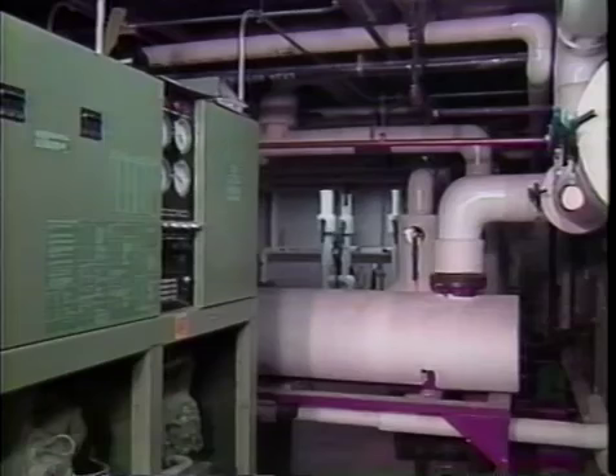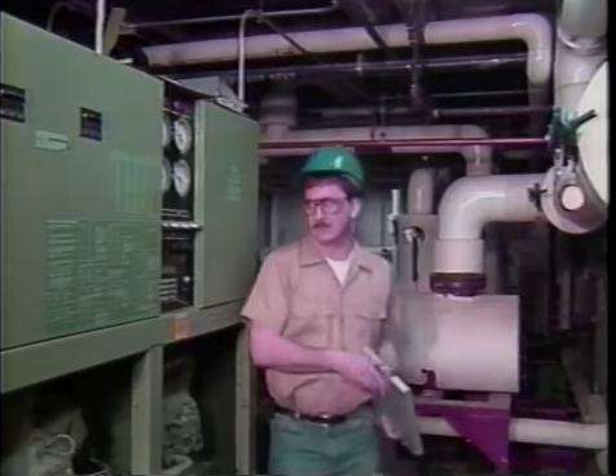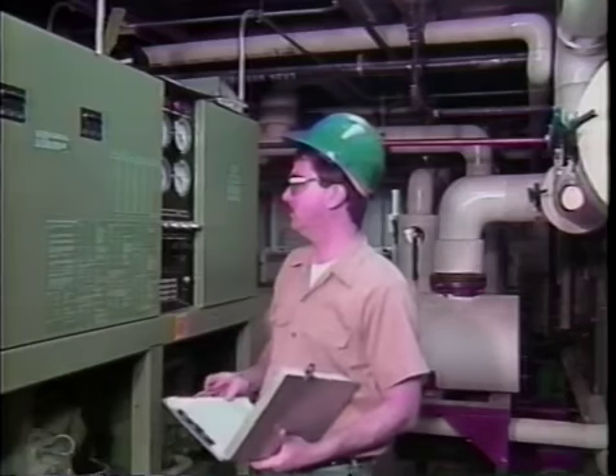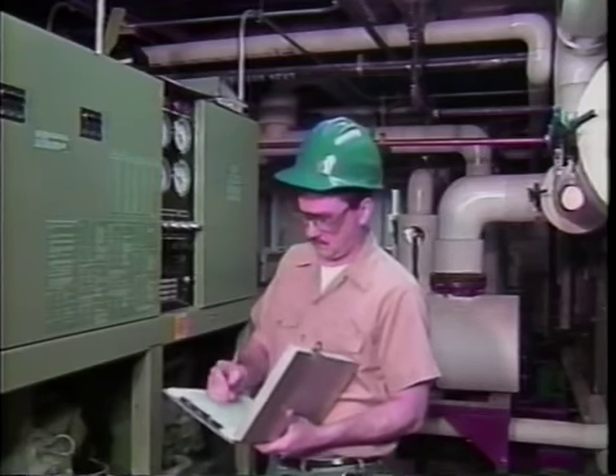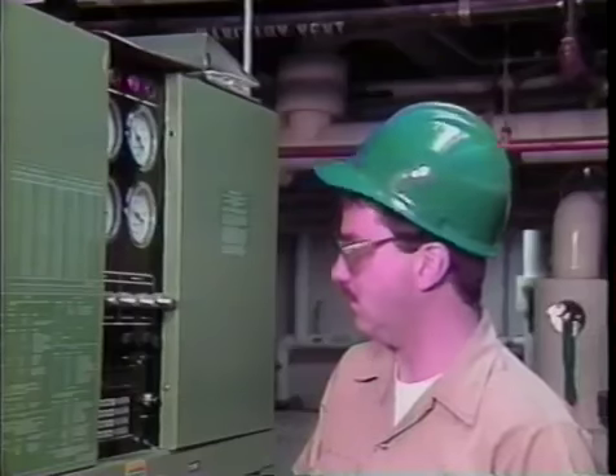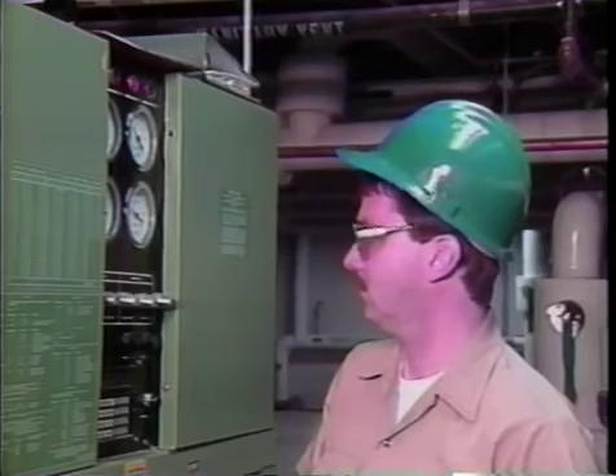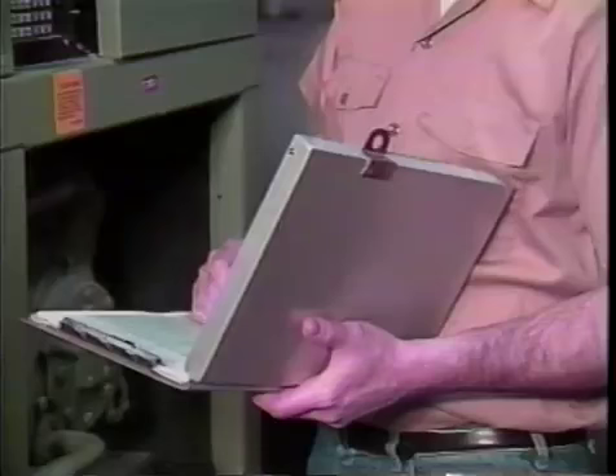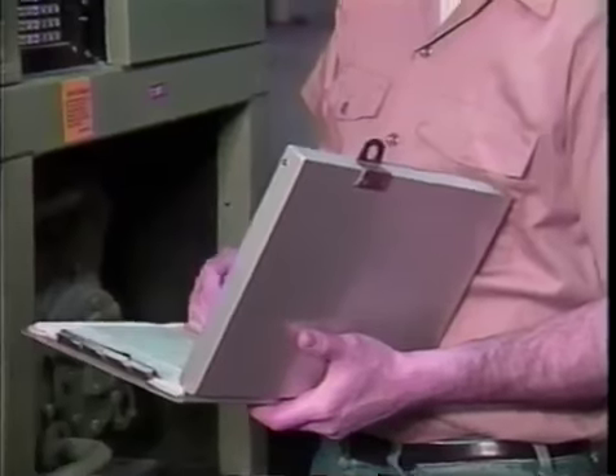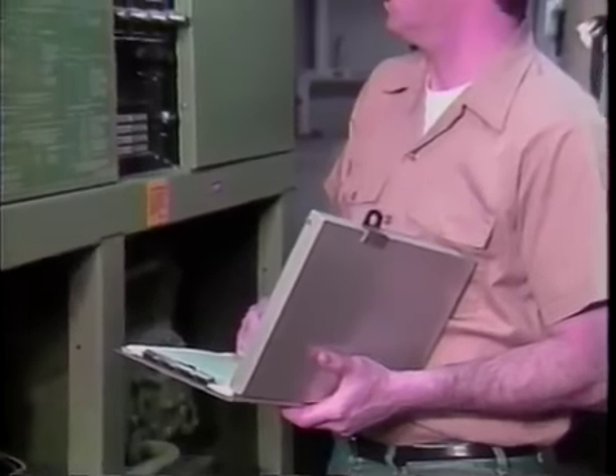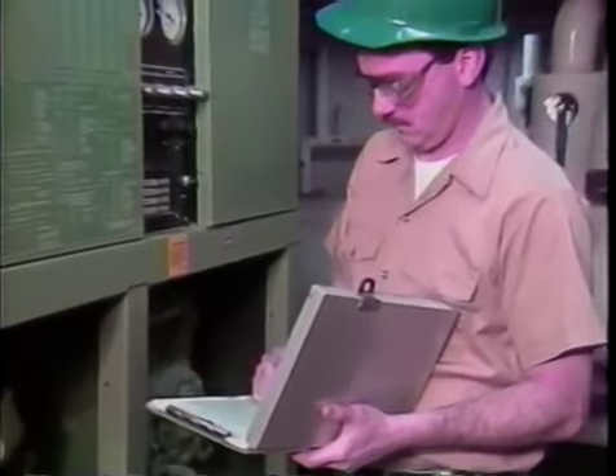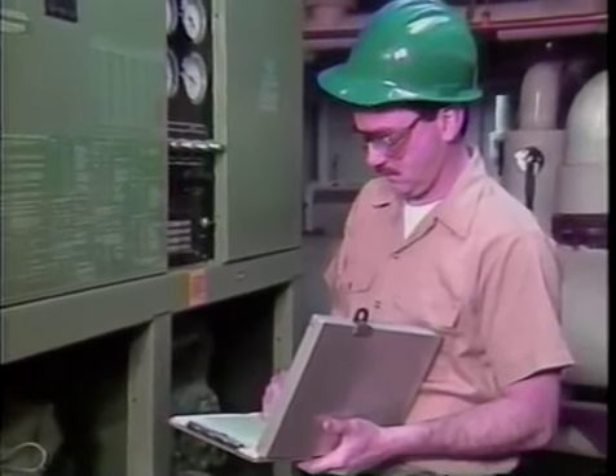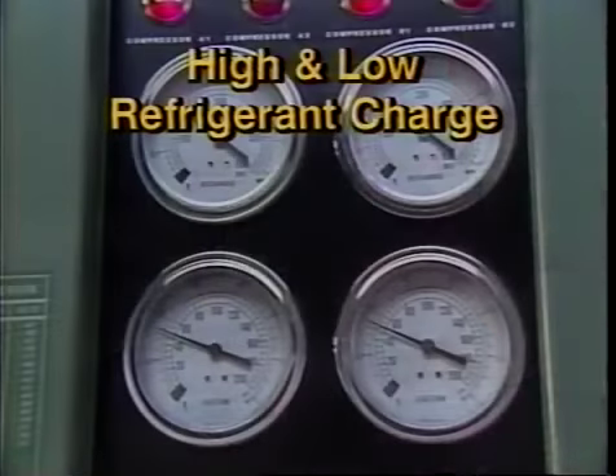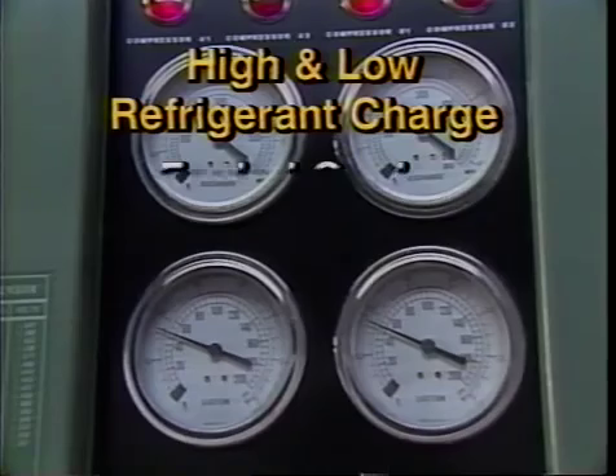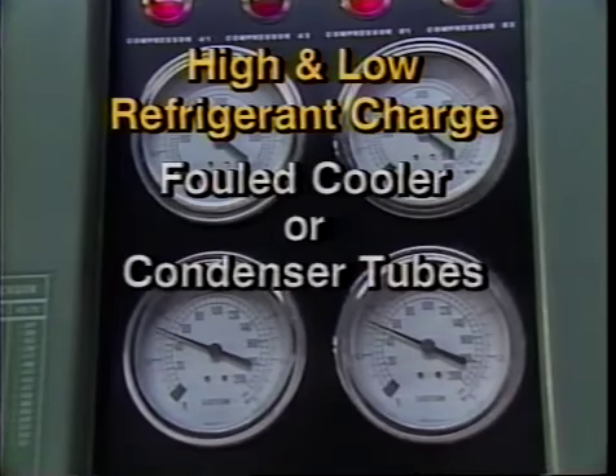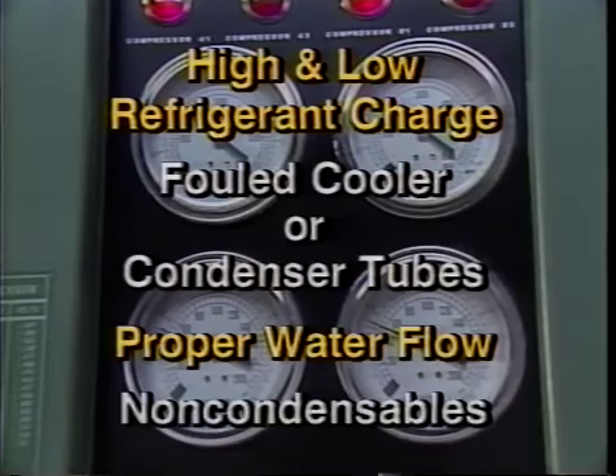chillers. In this program, we'll include a typical job visit and discuss the importance of maintaining a log. We'll also see how to use the log sheet to compare the design temperatures of the system to the actual system readings to provide troubleshooting information. Such information will show pressure and temperature trends to identify symptoms that point to chiller problems, including high and low refrigerant charge, fouled cooler or condenser tubes, proper water flow, and non-condensables.